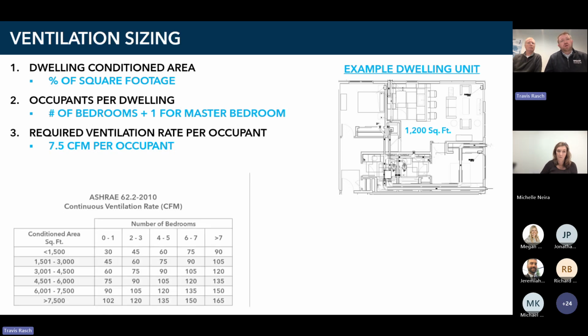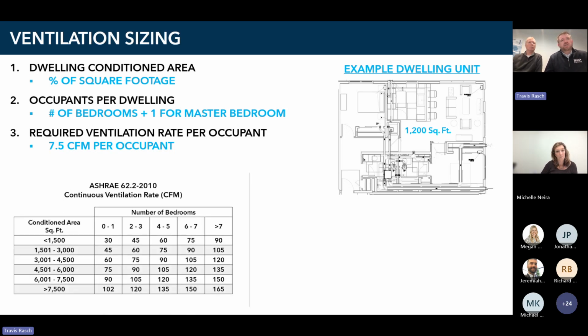We can use the simple table that ASHRAE provides in that 62.2 standard. So again, we've got less than a 1,500 square foot conditioned area here, as well as those 2 bedrooms. You can see here the continuous ventilation rate, if we use this table, is going to be 45 CFM. So that 45 CFM of continuous ventilation is what's going to be required for this dwelling.